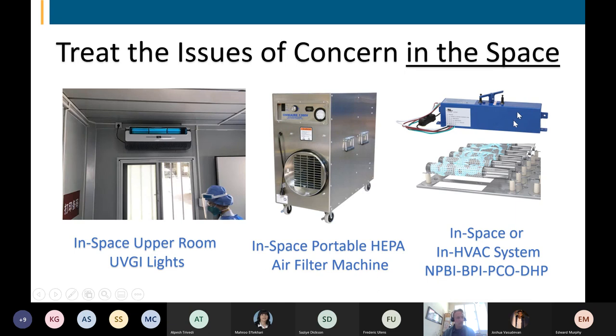And on the right-hand side of the screen, I have what I'll call advanced air cleaning technologies that can work both in the space, or some can actually be installed in the HVAC system and reach out into the space from there. Some of those technologies are needlepoint bipolar ionization, bipolar ionization, photocatalytic oxidation, dry hydrogen peroxide. There's a list of a few more that can be added to that specific category. They are not all the same. They do work differently from one another. It's important not to lump apples and oranges together in the same basket and then try to figure out what's what. Each has its own specific way of achieving results.